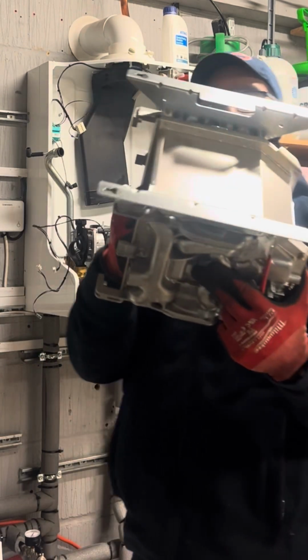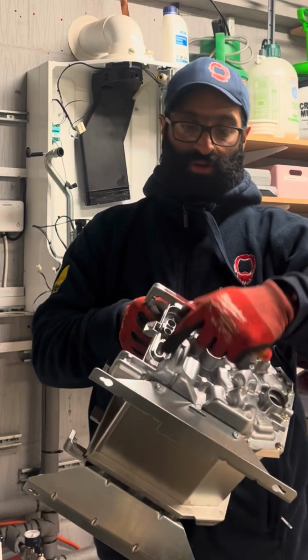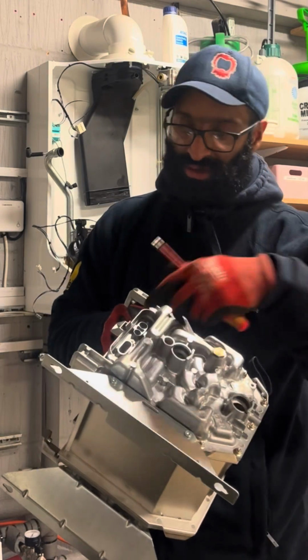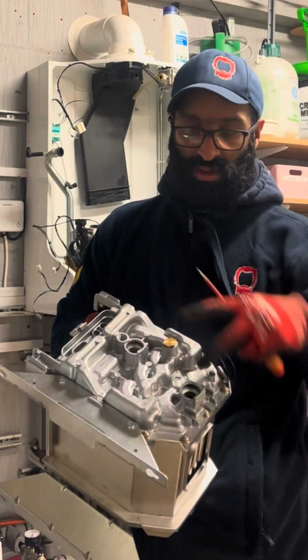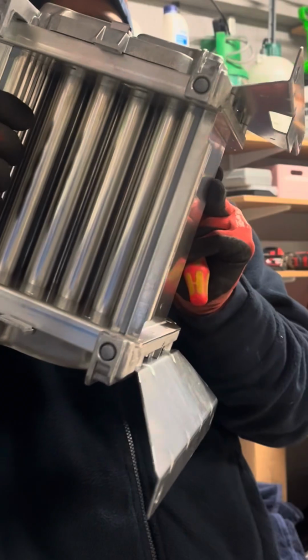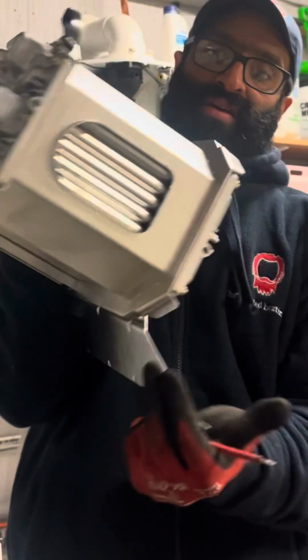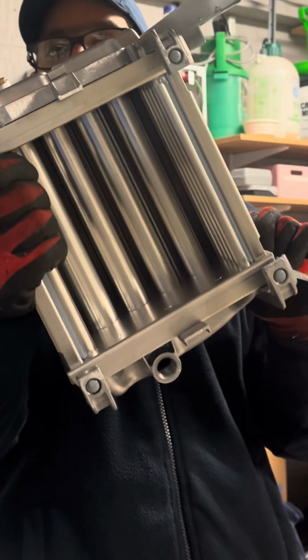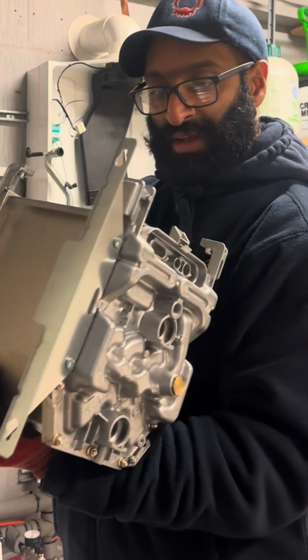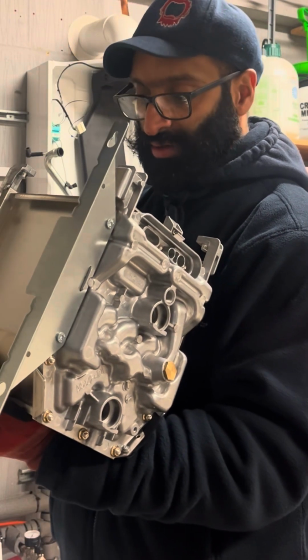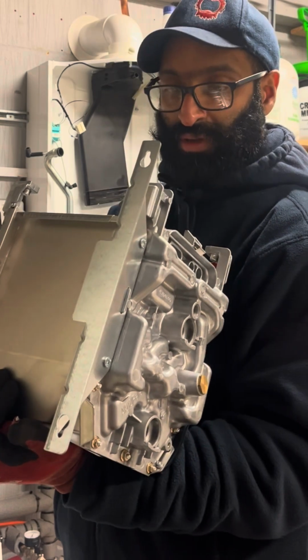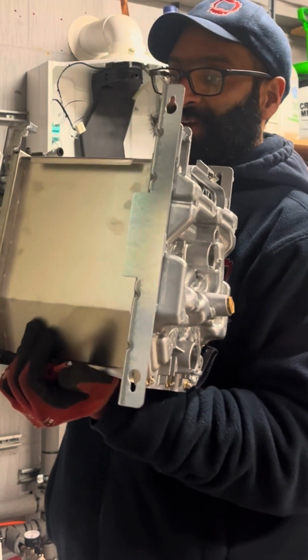And there's a new heat exchanger, so I just got to put the electrodes and sensor back into this one, hang it, and then put the pipes back in. So that's the inside of an Atag heat exchanger, stainless steel. I've replaced a few of these now in the last couple of months - something is definitely not right with the manufacturing of them.